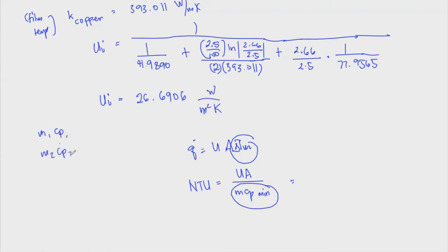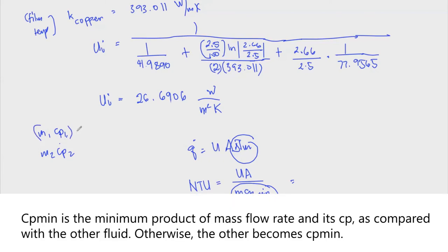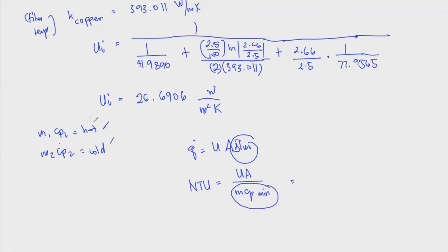NTU equals U·A divided by (ṁ·Cp)_min. This ṁ·Cp_min is simply the mass flow rate of the fluid that gives the minimum value when multiplied by its Cp. There are two cases: the hot fluid and the cold fluid. The one giving the lower value of ṁ·Cp is C_min; the other is C_max. They can interchange depending on the result, so we can't say in advance — it depends on the answer.